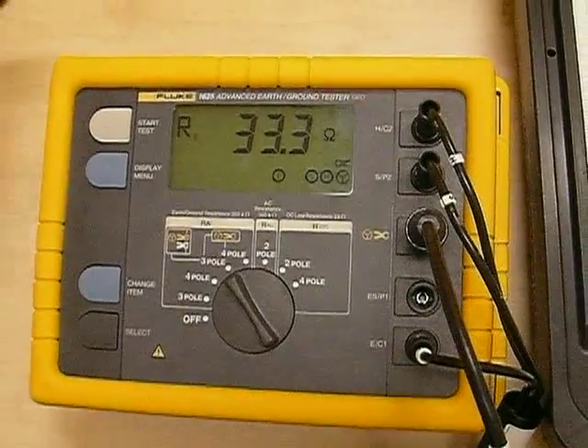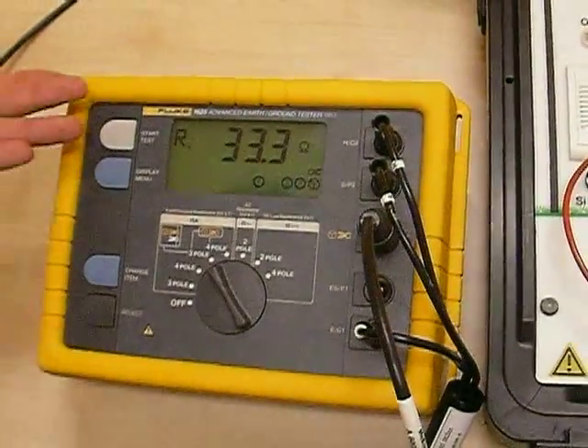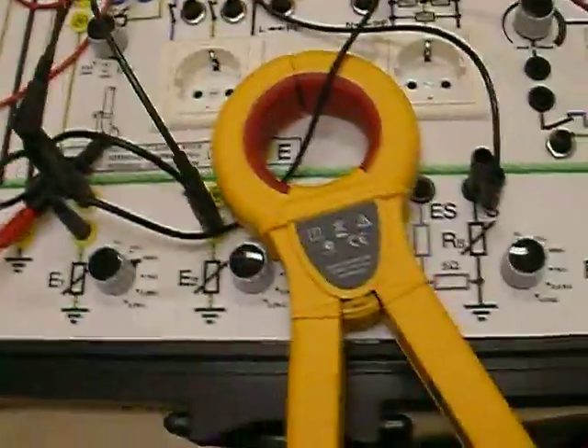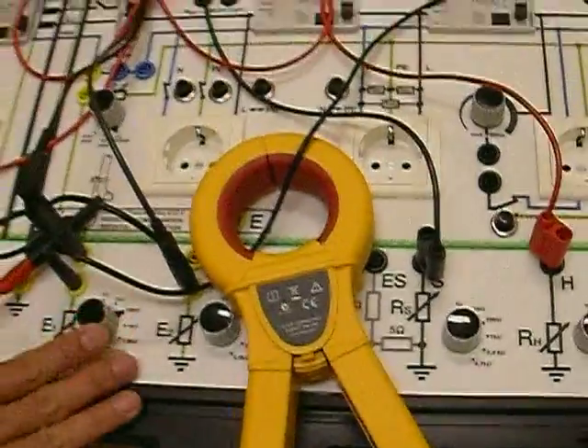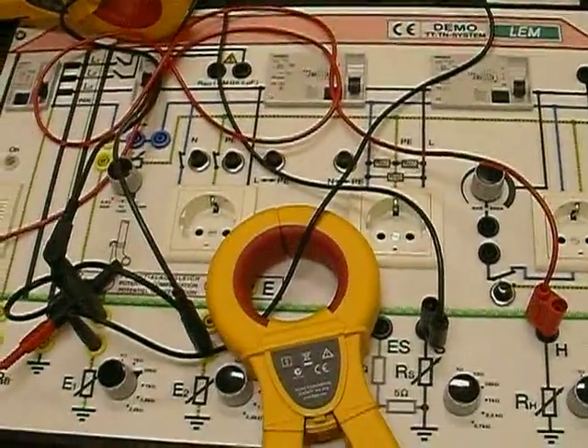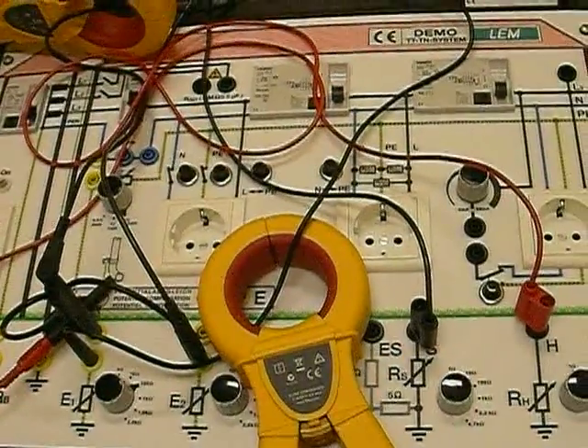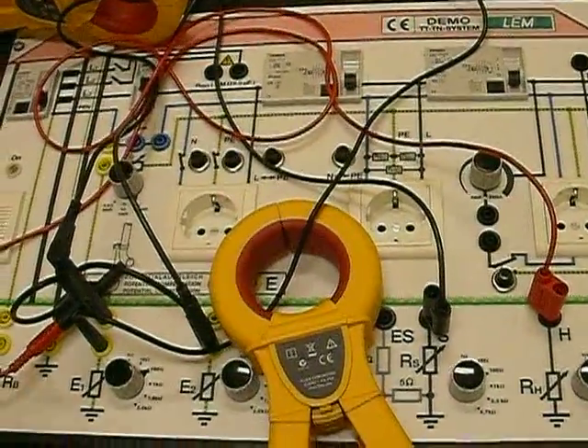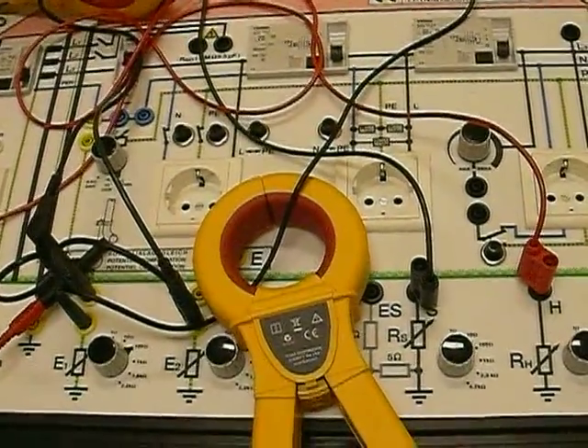Yeah, so we find that this one is deteriorated. We are able to tell that one of these rods is having a problem because the reading is a lot different compared to the other nominal resistance.